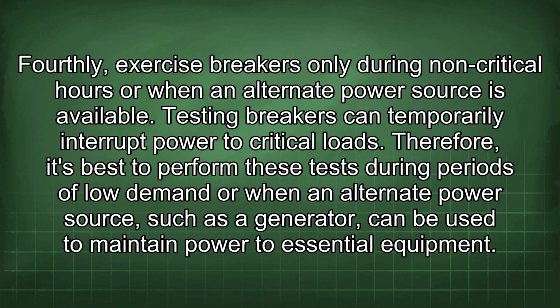Fourthly, exercise breakers only during non-critical hours or when an alternate power source is available. Testing breakers can temporarily interrupt power to critical loads. Therefore, it's best to perform these tests during periods of low demand or when an alternate power source, such as a generator, can be used to maintain power to essential equipment.